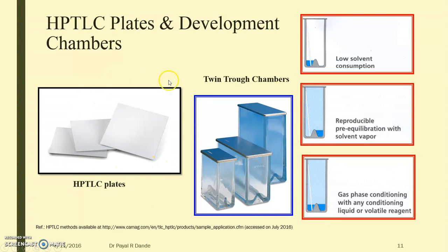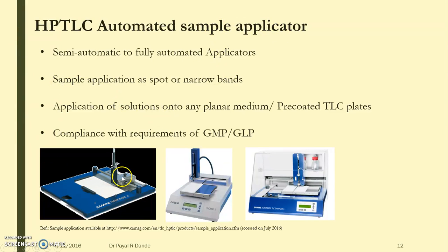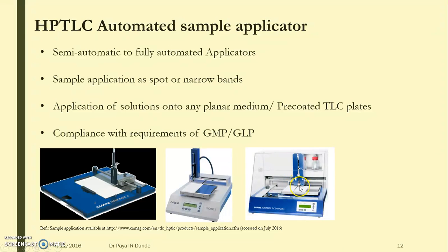These are the advantages and sophistications available with HPTLC instrumentation. Next, we come to the sample applicator. There are several sample applicators available. Earlier we used semi-automated applicators and now we have fully automated applicators. In semi-automated applicators, the manual parts were cleaning the injector, filling it, and placing it; the rest was programmed in terms of quantity to be applied and distance. Nowadays, with completely automated samplers, the sample is automatically filled in the injector and once the program is set, it applies the sample onto the plate as per the program in terms of distance and number of spots.